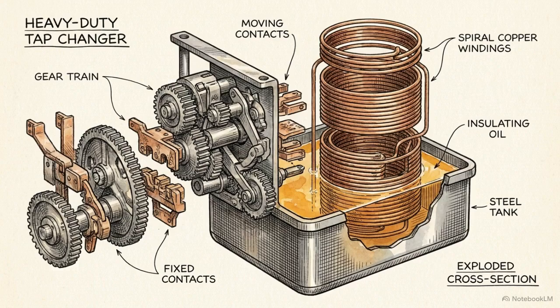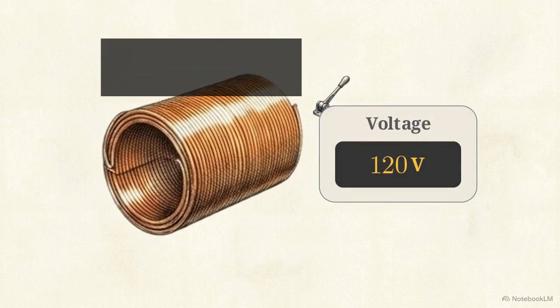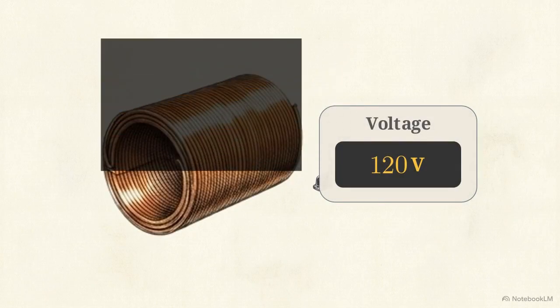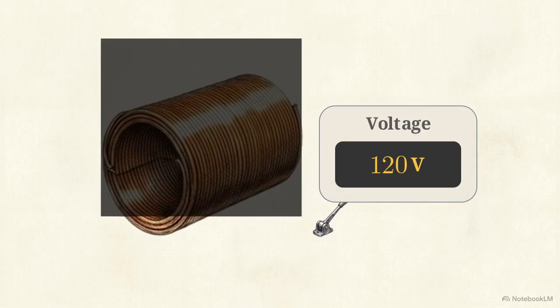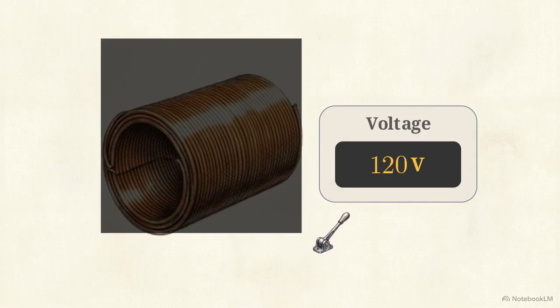To do this, they install internal mechanical switches, known as tap changers. These mechanisms dynamically add or subtract active turns from the winding, allowing operators to precisely dial the voltage output up or down on the fly.